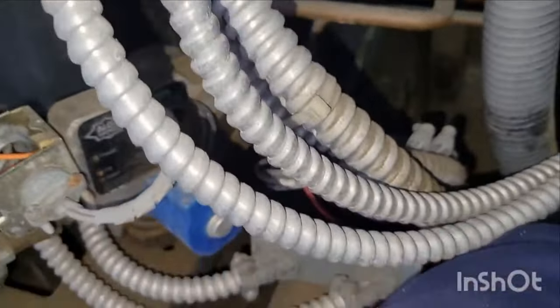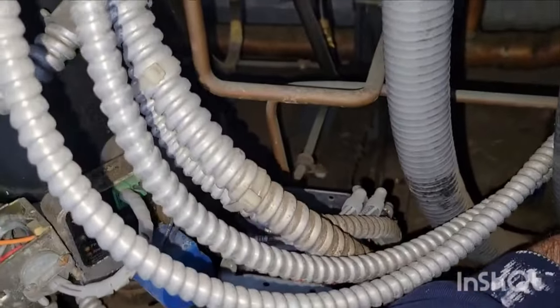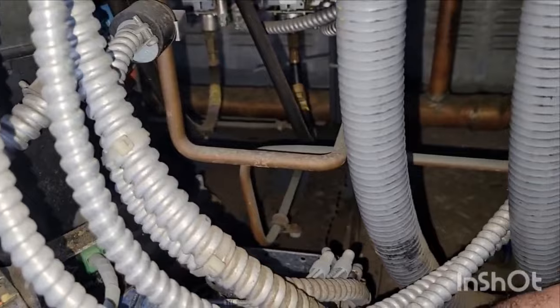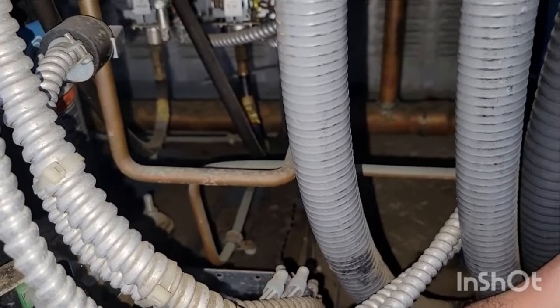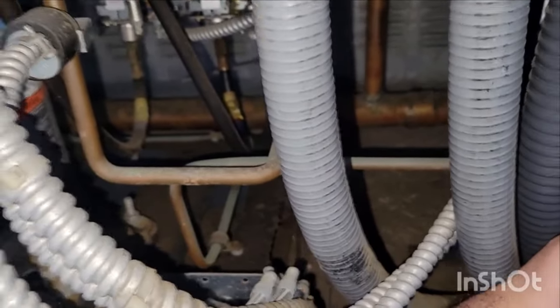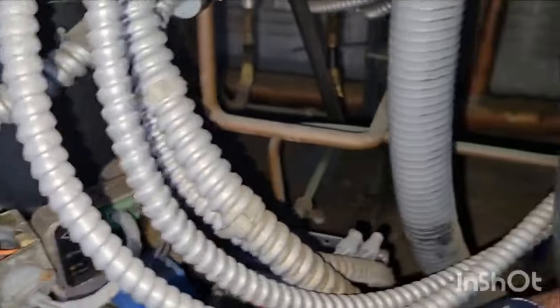So that's why I always check my compressors first, because let me tell you, the longer you live in this trade, people don't isolate compressors properly. It's just a thing. People don't do it. Assuming that your friend or your coworker will, they don't do it. They're not gonna do it. You're gonna be out on call. They're not gonna do it. People don't isolate compressors properly, and this seems to be another case of that.